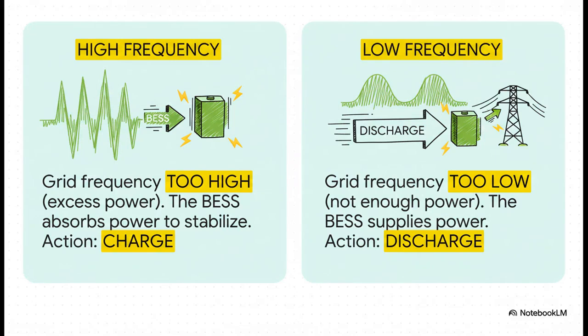What's really mind-blowing isn't just what it does, but the speed at which it does it. For its most important job, frequency regulation, a BESS can react in as little as 200 milliseconds, literally faster than you can blink. If the grid frequency spikes, it instantly starts charging to absorb that excess power. If the frequency dips, boom, it's discharging. It's this constant lightning-fast balancing act.